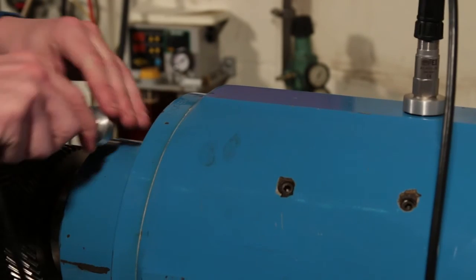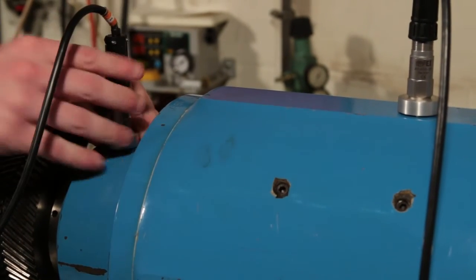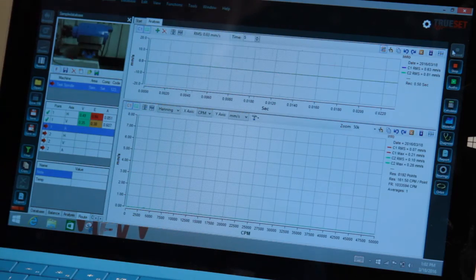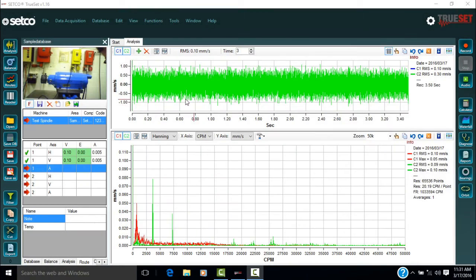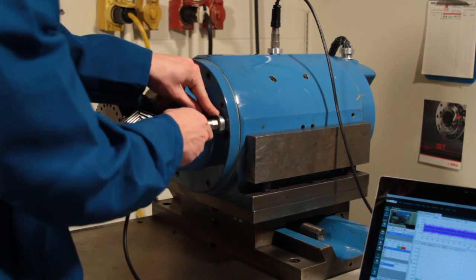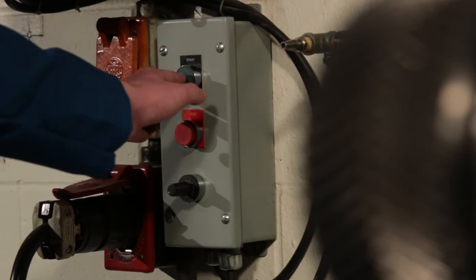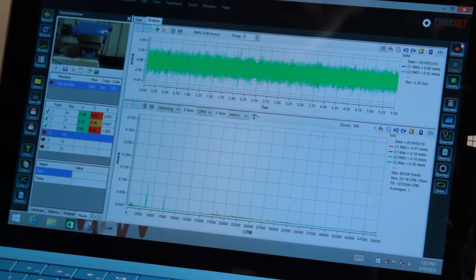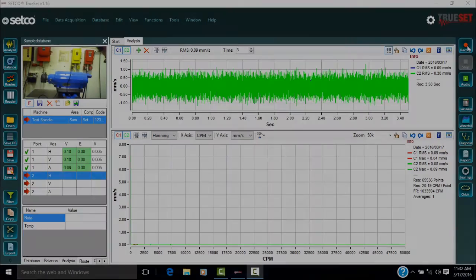Stop the equipment and move the accelerometer from horizontal to vertical to match the next axis in the route. Start the equipment up again and press record again. The data is displayed on the two graphs. Once again, stop the equipment. Move the accelerometer from vertical to axial to match the third axis in the route. Then, restart the equipment and select the record function. The data is shown again on the graphs.